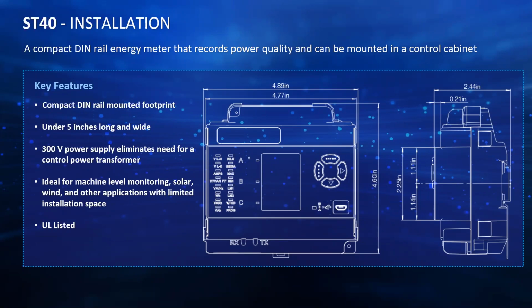Or if you just have an application where you want the meter installed but don't necessarily want people to see there's a meter, this meter is very easy to hide out of the way. You still have the communication capabilities, but nobody who has access to that room needs to know the meter is in there. It is DIN rail mountable. You do not have to cut any holes in panels. Just as long as you have a rail, or you can simply install a rail that's a couple inches long, mount the meter on that, wire it up, and it is good to go. This meter is also UL listed.